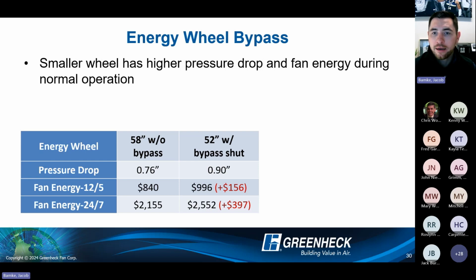The one thing to keep in mind, and one that is incredibly important in the Washington market due to the Washington State Code, is you have certain energy effectiveness minimum requirements as well. And when you shrink your wheel down to this 52-inch, you're going to lower your overall effectiveness at the same time. So you're lowering your effectiveness, which means that you're going to require more heating capacity downstream. And then you also have more fan energy during normal operation as well.